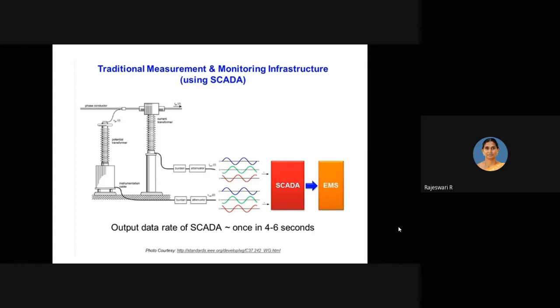So what does SCADA mean? SCADA technology, or the SCADA network, is actually software acquiring analog signals from CT and PT, which are connected at the point where we want to track information, through the remote terminal unit connected at that particular point. So SCADA is giving the data to the EMS.